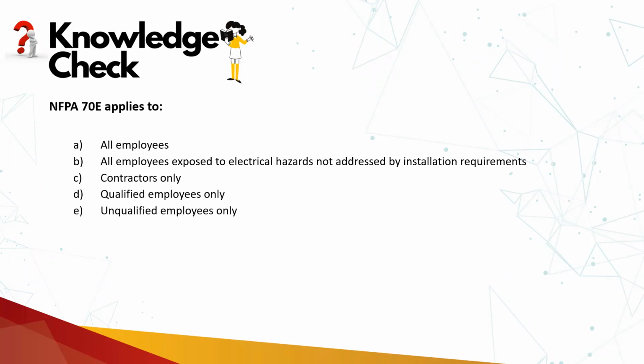So we have seen one picture in which the breaker was installed and no one was interacting. When you open that MCB or the panel in order to see if any switch or any fuse has blown, or if any short circuit has happened, and so on, then the responsibility shifts from NEC to NFPA 70E. So NFPA 70E is responsible for all employees who are exposed to electrical hazard which is not addressed by the installation requirement.